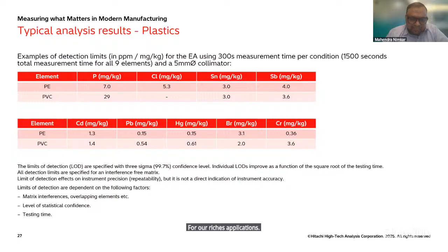Similarly, for metals, as I mentioned, for aluminum alloys or brass, the LODs are very low compared to the asking value. If you look at lead and mercury, the asking value is 1000 ppm, but here the LOD for lead is like 5 or 6. So it is a very good analytical tool, based on LODs, for checking RoHS compliance. It is not only about RoHS, but there are many other compliances also. When you talk about REACH testing, for example, there are so many banned materials which you cannot test with XRF.